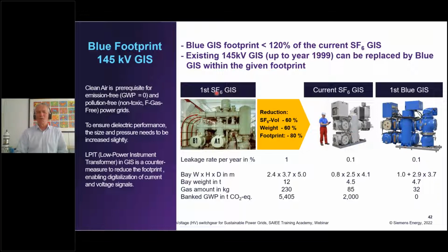I just want to show you how a GIS looked like which was installed 50 years ago, in 68. It had a bay width of 2 meters 40. That's quite a big bay width. And the latest SF6 technology, which is built and offered today, has a bay width of 800 millimeter. And how much wider is the clean air technology? The clean air technology is at 1 meter. So we do have a higher size and bay width than today's SF6 technology, but compared to the early days of GIS technology, it's still much smaller.